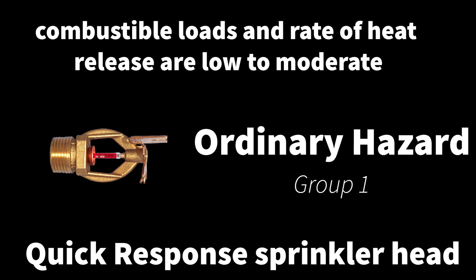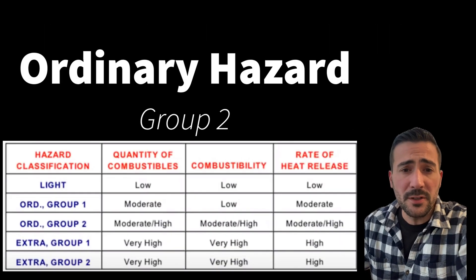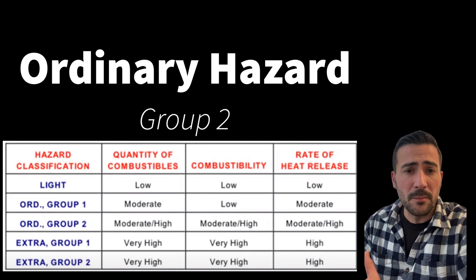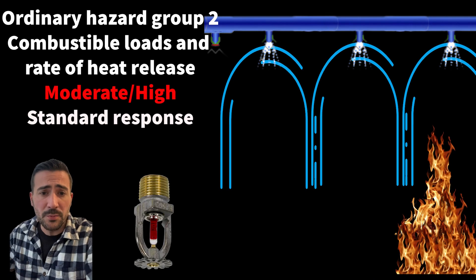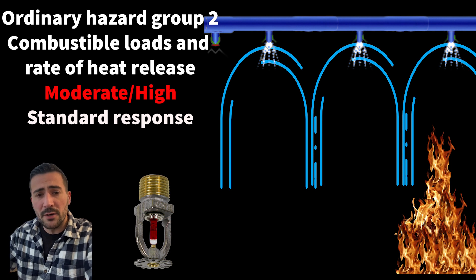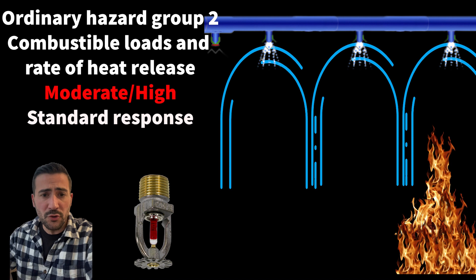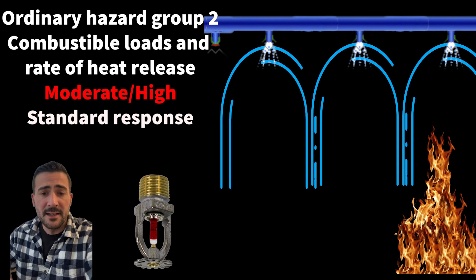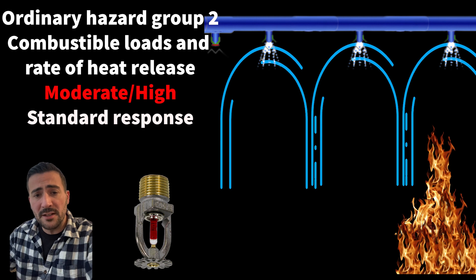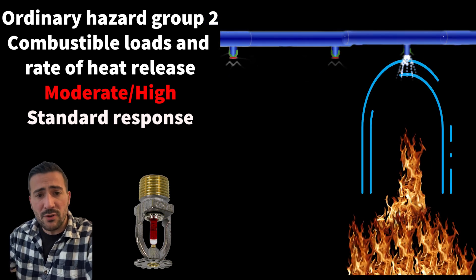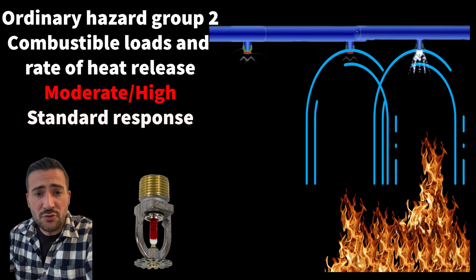Ordinary hazard Group 2 goes to moderate-high on combustible loads and rate of heat release. For this reason, we're going to use the standard response sprinkler head. Take a look at this picture — you can see a fire in the corner but all the sprinkler heads are going off. This has been proven to happen when you use a quick response in ordinary Group 2 or extra hazard occupancy, where combustible loads and rate of heat release are on the high side. The theory is too many heads going off at the same time taxes the system's pressure, causing it to be less effective on controlling the fire. When we use a standard response head, the right amount of heads go off in the correct locations, proving to be better at controlling and putting out the fire.